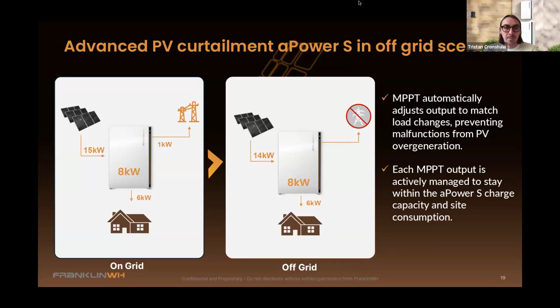In an off-grid situation, we're able to manipulate the MPPTs to balance the charge rate with the site's consumption. If this orange triangle in the center represents an instantaneous grid outage, we'd be able to ramp down PV production to keep as much online, charging the battery at its peak rate while meeting the home load.